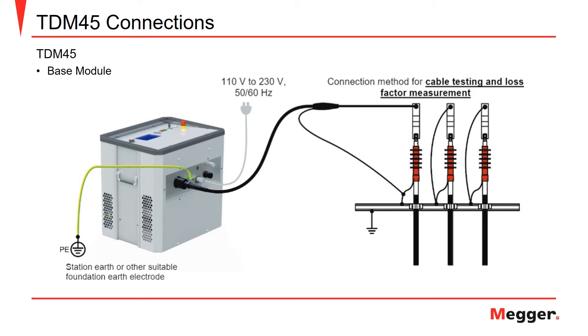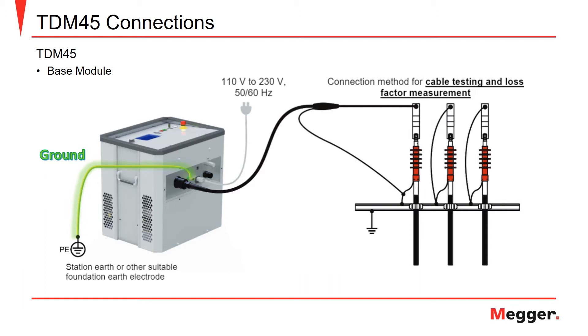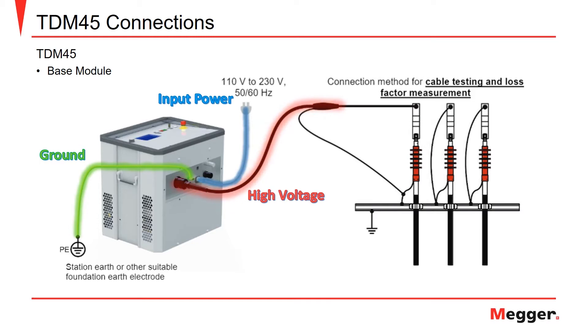In the first example, we have the typical connections required to perform a VLF or tan-delta test using the TDM45, which is comprised of the base module and the necessary connections. These connections include the grounds from the base module to the station ground, the input power to the instrument, and the high-voltage cable going from the base module to the cable under test.